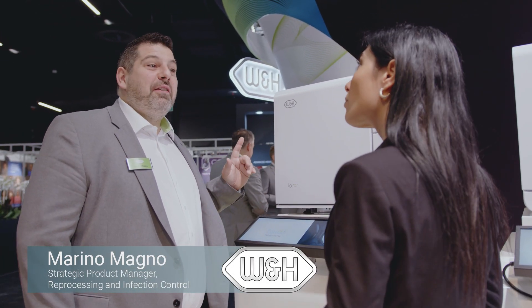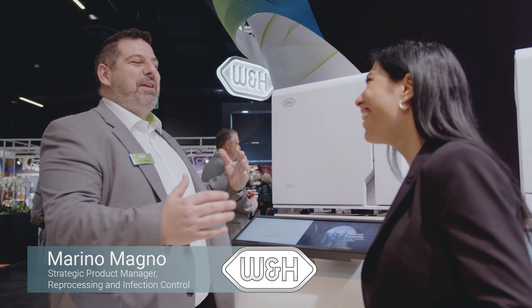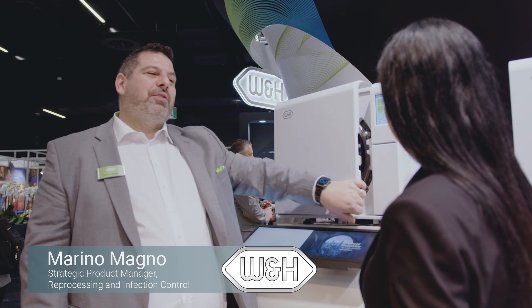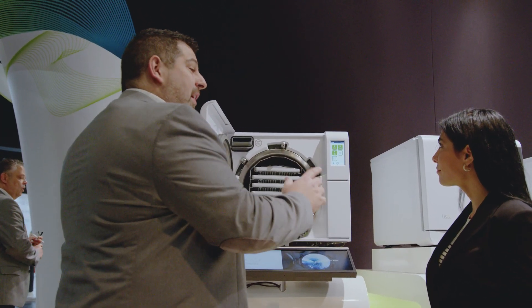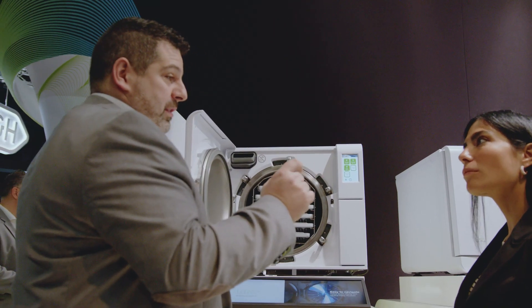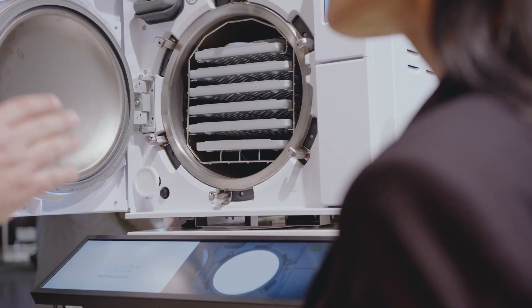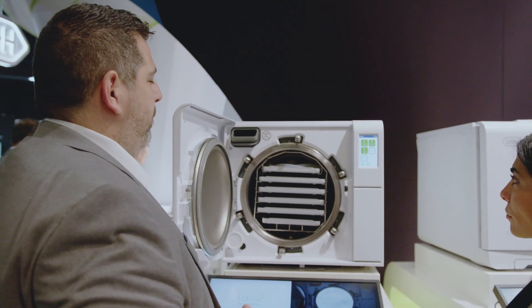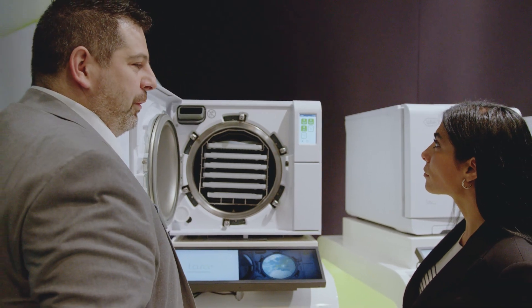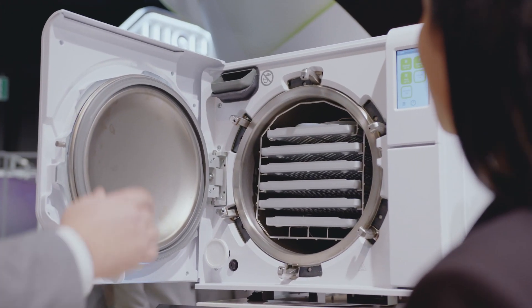LAR-XL. XL stands for exceeding the limits — not only because it's bigger. If you look at the magnitude of the chamber, it's 11 inches instead of 10 inches, so 2.5 centimeters more. The real good thing is the same footprint, so you can put it in each type of furniture without any problem. And another feature of this device is the inlet of the water just in the front.